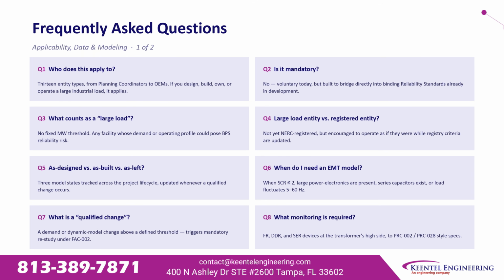Who does this apply to? 13 entity types. If you design, build, own, or operate a large industrial load, it applies. Is it mandatory? No, voluntary today, but built to bridge into binding reliability standards already in development. What counts as a large load? No fixed megawatt threshold. Any facility whose demand or profile could pose reliability risk. How is a large load entity different from a registered entity? Not yet NERC registered, but encouraged to act as if it were.